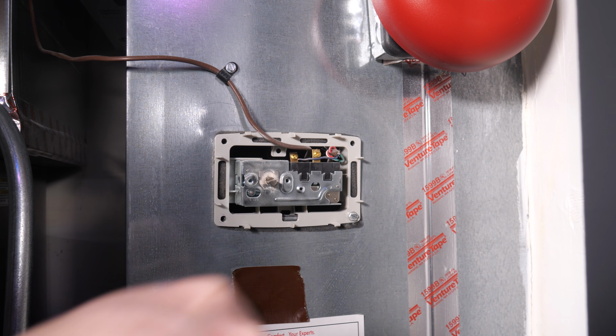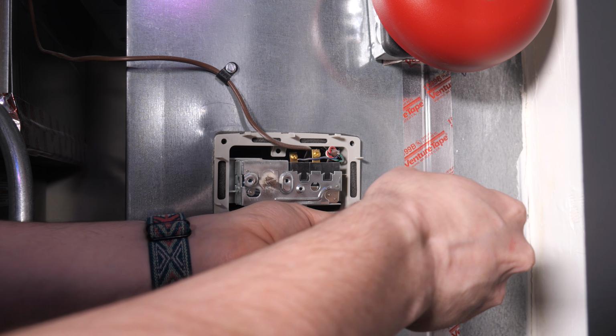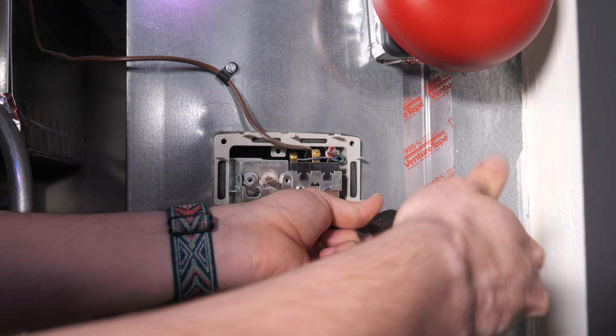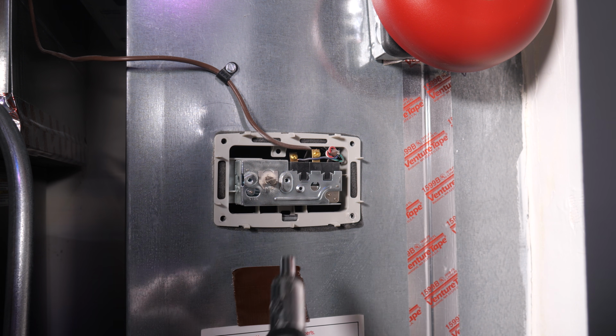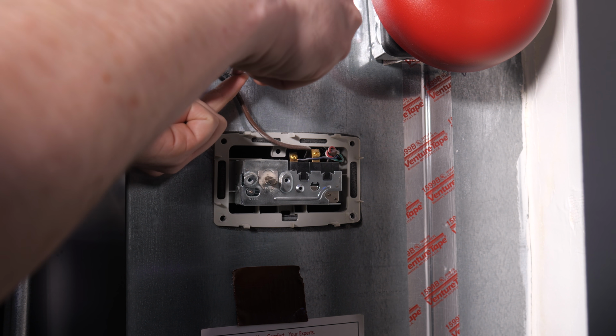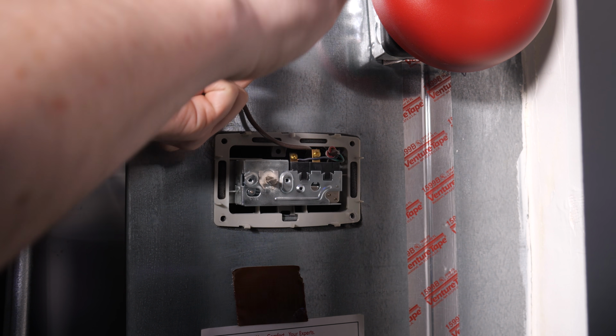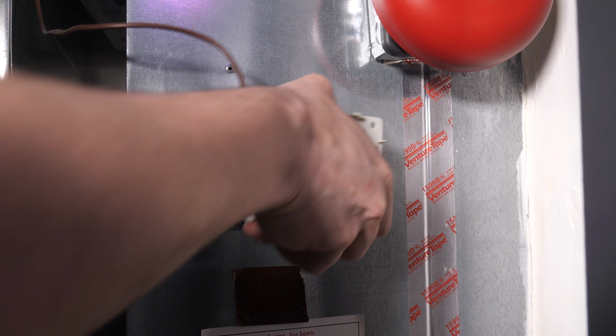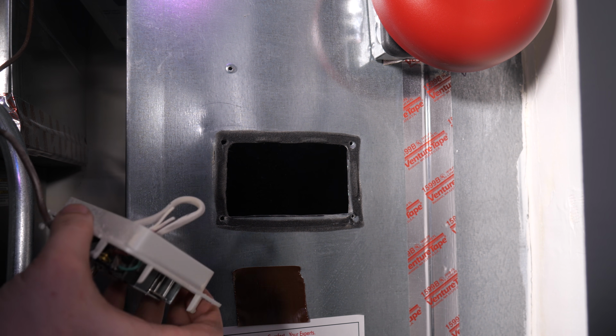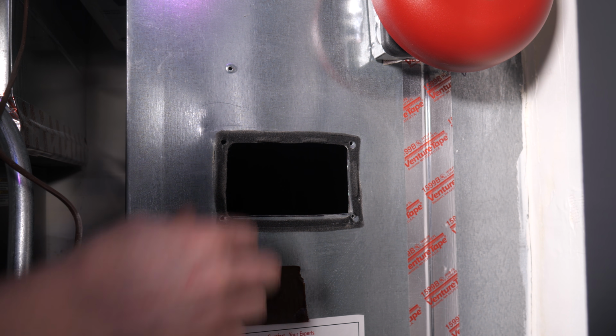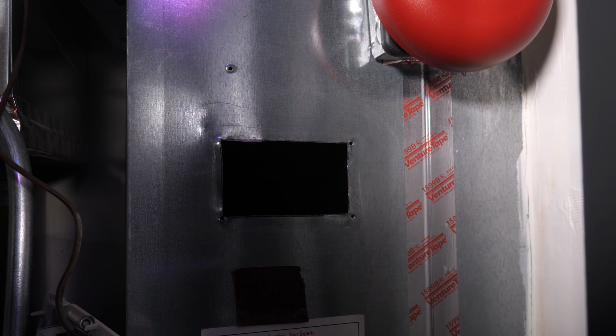Alright, with the outdoor temp sensor in place, it was time to install the new humidistat. It needs a 3/4 inch hole in the return duct to get a measurement of relative humidity. I was hopeful the existing humidistat would have a similar hole underneath, but no, that one needed a big ol' hole cut in the sheet metal, which now presented me with a problem.